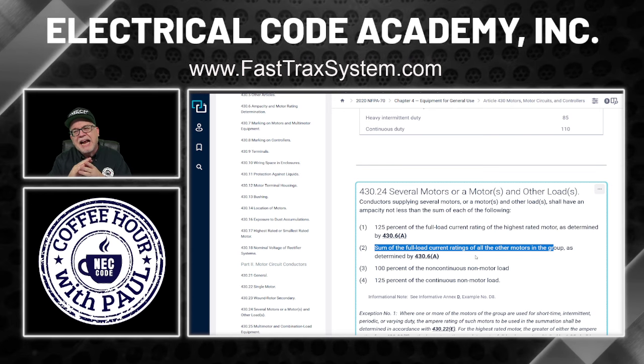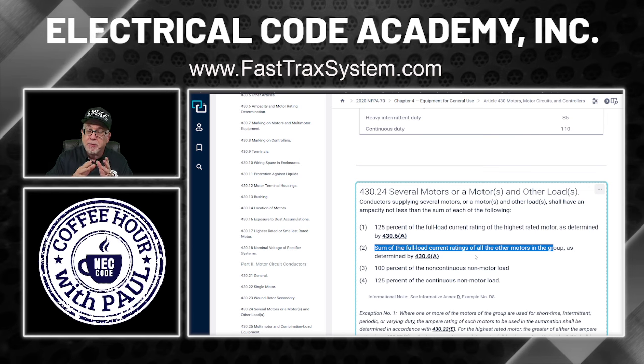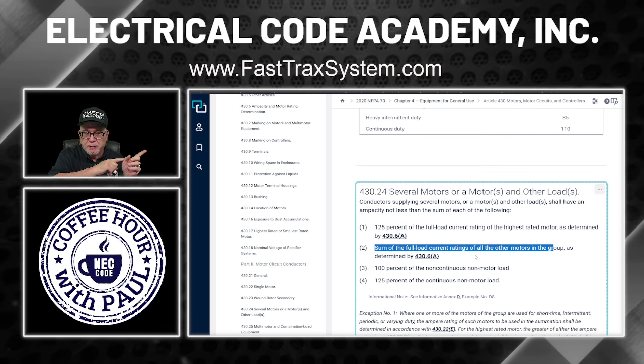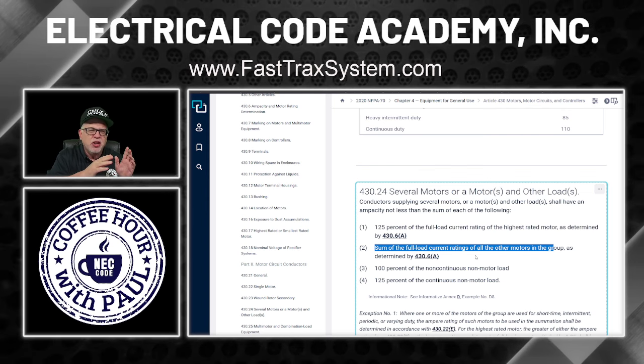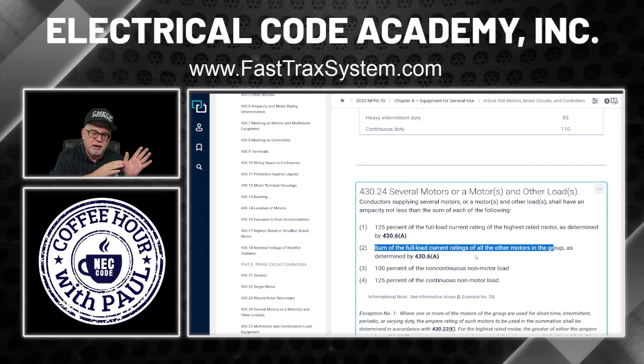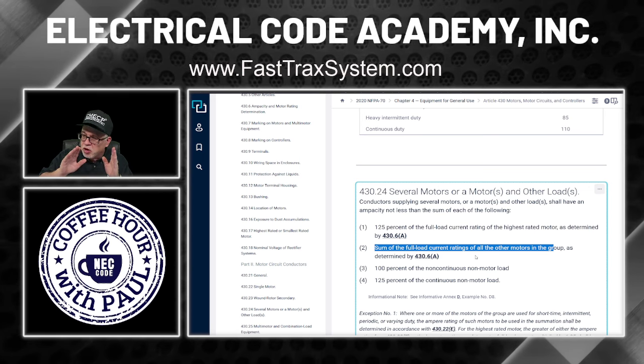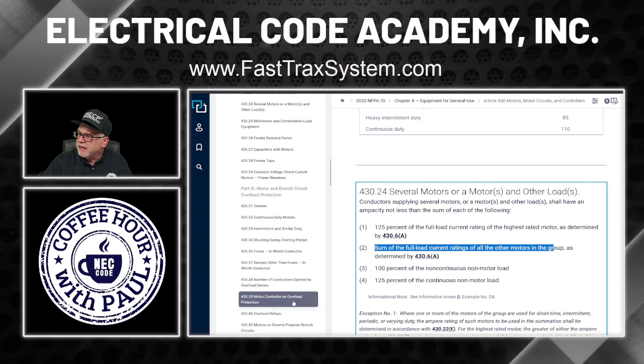But now I need to know what the FLC is, full load current. And remember, that's in the code, not on the nameplate. That's full load amps. We use that for overloads, and we'll use it also for unique motors like intermittent duty, periodic duty, and all of those things that are also in 430.22(E). But that's for a whole different episode. Here, we know what we're looking for, so we're going to go to those tables. Let's do it right now.